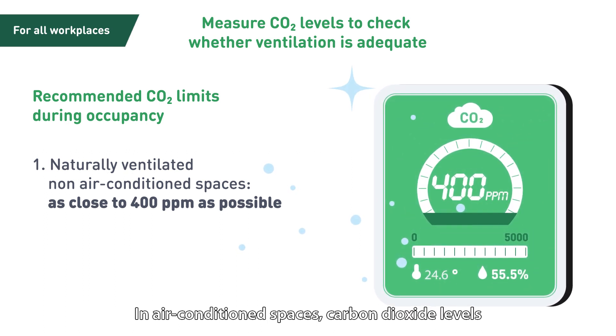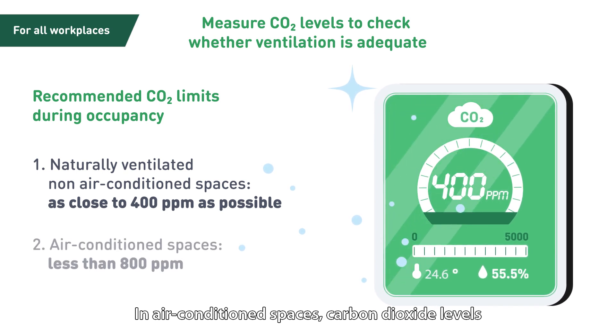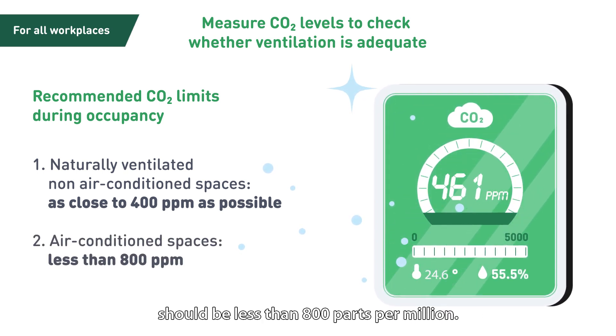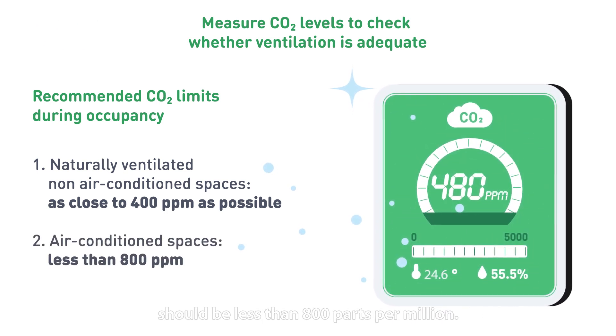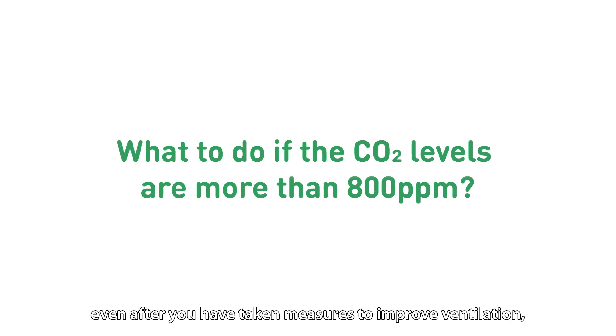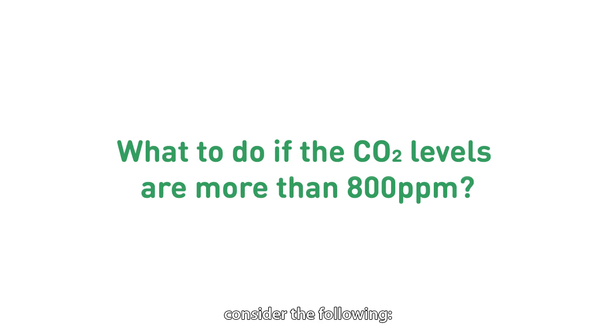In air-conditioned spaces, carbon dioxide levels should be less than 800 parts per million. If carbon dioxide levels are above the recommended levels, even after you've taken measures to improve ventilation, consider the following.